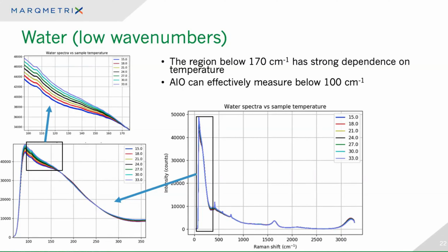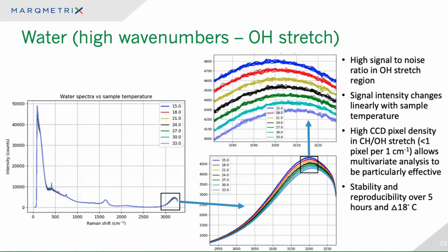We take that same information and we go out to the OH stretch. So the OH stretch of water starts at about 3,000 wave numbers. It peaks at about 3,300. You don't usually see this with a 785 nanometer Raman system because the detector is usually blind as we go past 3,000 wave numbers. But here we see the same response and another water peak in its sensitivity to temperature. Also look at not only the sensitivity at that wavelength for water, which is a weak scatter, but also the reproducibility as a function of temperature.